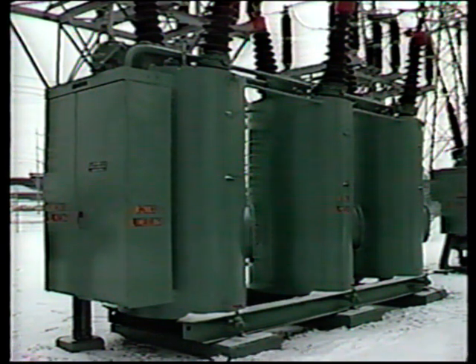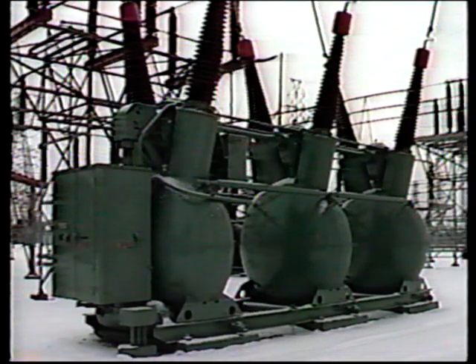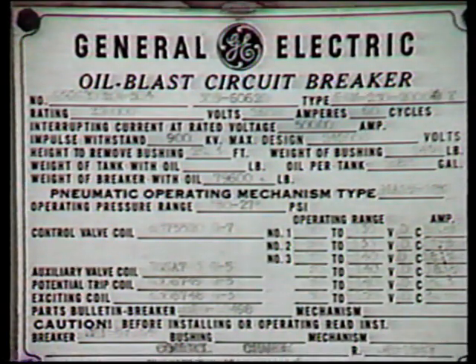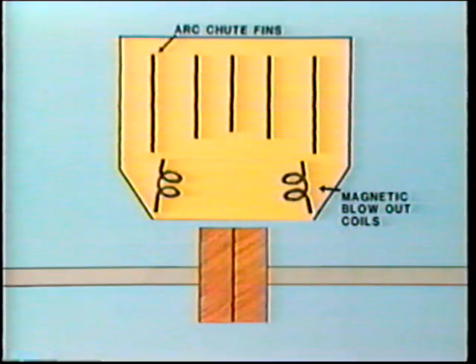In fact, for the protective relay to have any impact at all on the power system, it must be coupled to a switching device. The exception to this is where relays are used to give alarm only. But for action, it must command a switching operation. Conversely, the circuit breaker would have little value other than as a manual switch if it were not coupled to protective relays. The circuit breaker is specifically designed to interrupt fault current, which may be 10 times or more than normal full load current. It achieves this by breaking the current flow in a specially designed interrupter.